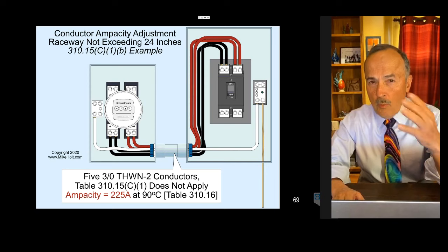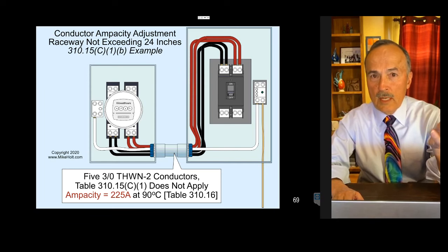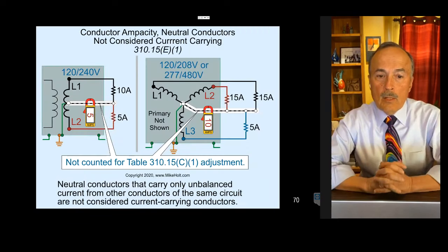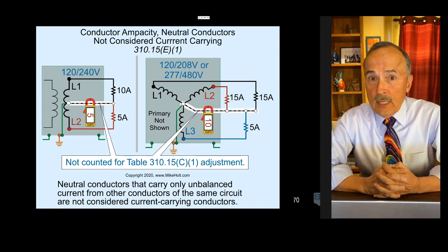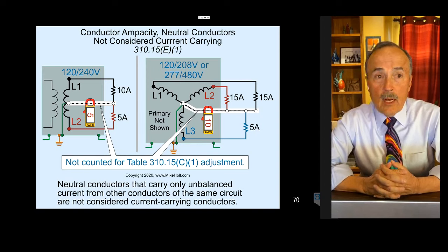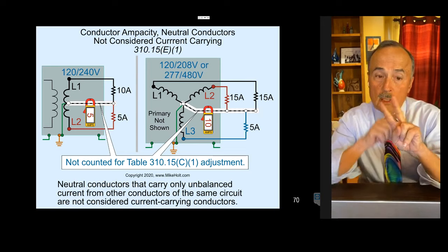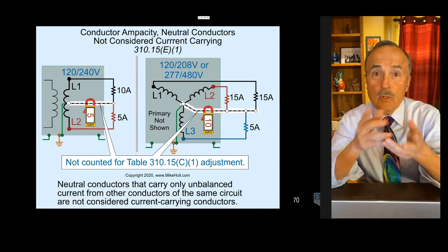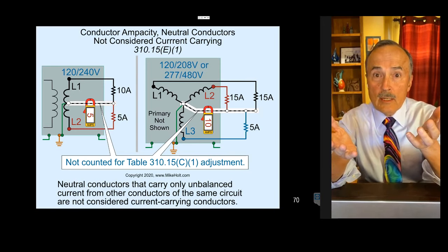They just disconnected the sheath, put them in the connectors, and brought them all together into a 2-inch raceway, not longer than 24 inches. We don't have to adjust the ampacity. Just kind of bringing that concept so when we get to that question about the Romex, we have a better idea.